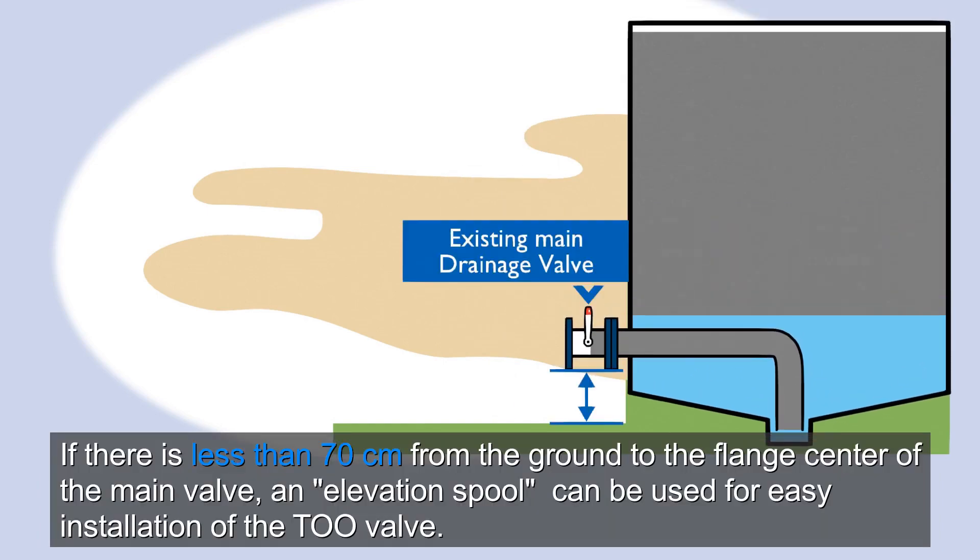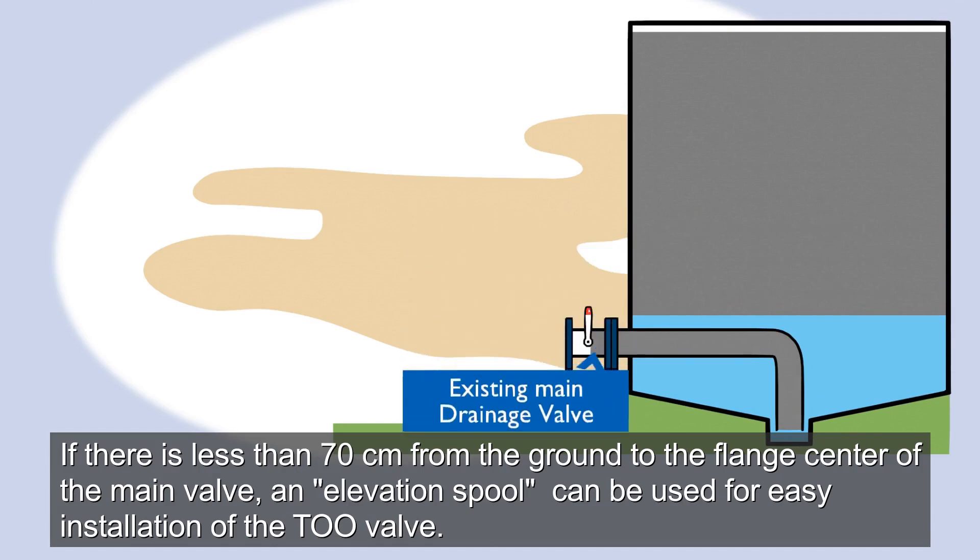If there is less than 70 cm from the ground to the flange center of the main valve, an elevation spool can be used for easy installation of the TOO valve.